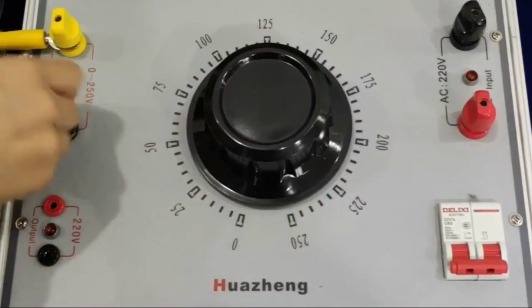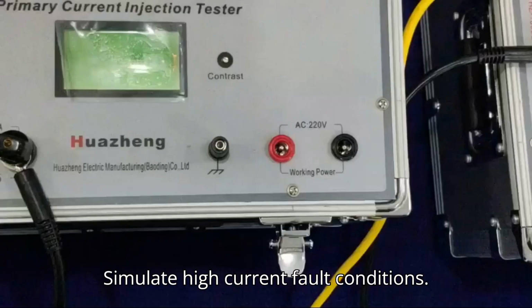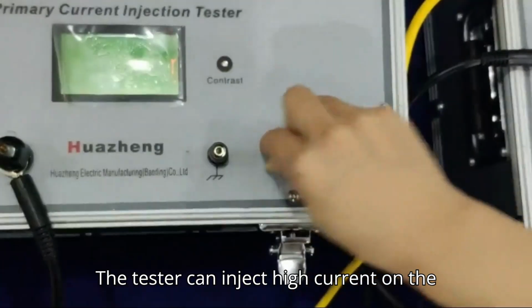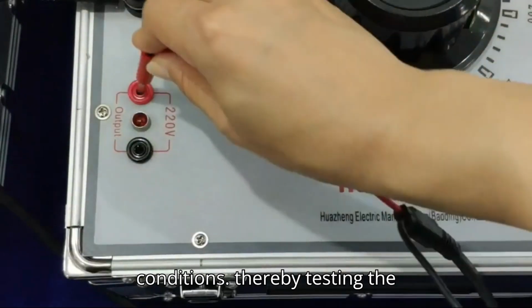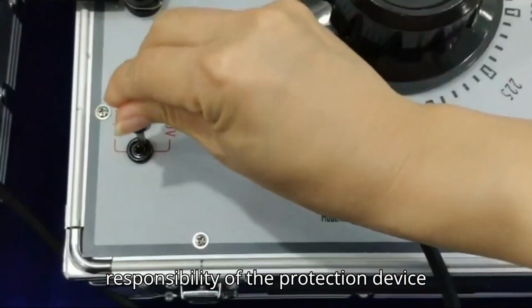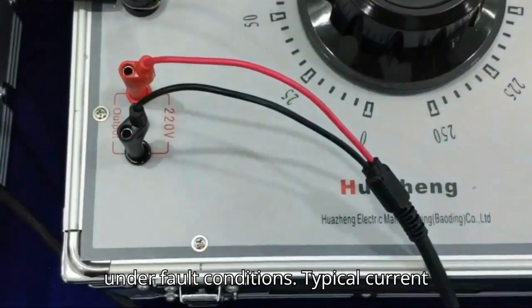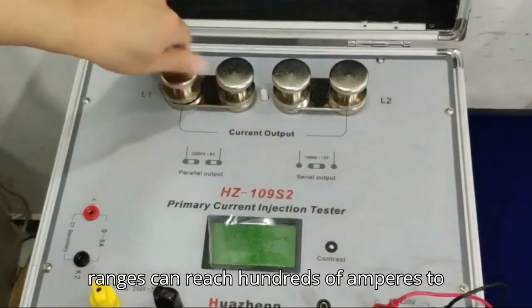Main features. Simulate high current fault conditions. The tester can inject high current on the main side, high voltage side, of the power equipment to simulate fault conditions, thereby testing the responsiveness of the protection device under fault conditions. Typical current ranges can reach hundreds of amperes to thousands of amperes.